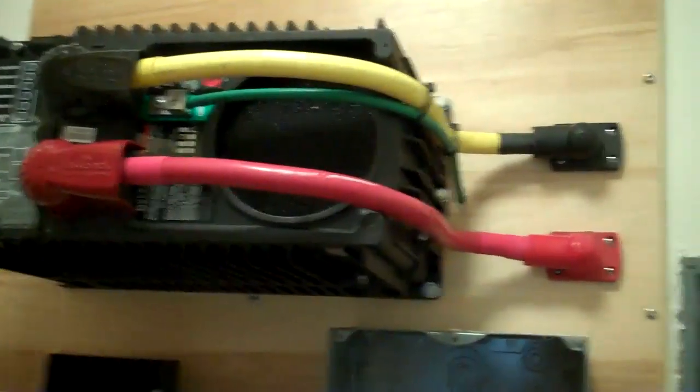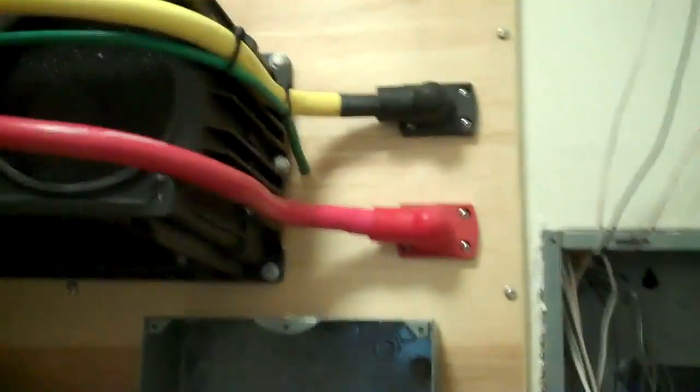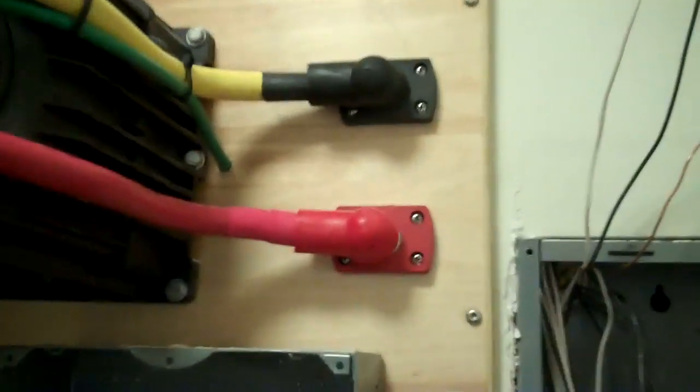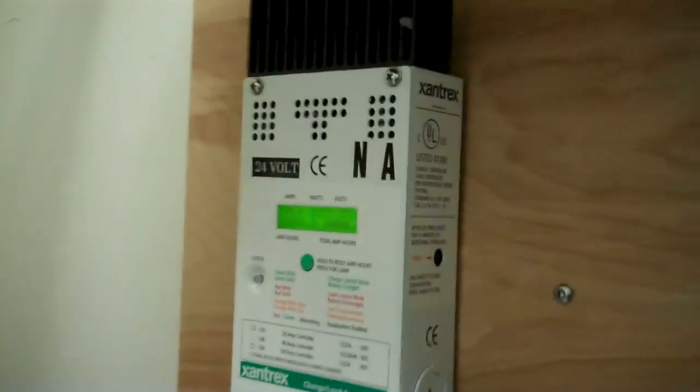We're done with the DC side of the inverter, it's hooked to those pass-throughs, it comes down, this is all in 4-Aught cable. Those two yellow are actually negative and positive, but we didn't have any red 4-Aught, but we wanted to keep running 4-Aught. Got the charger back up and running, hooks to the batteries over here with 4-Aught. But I'm going to overview some of that, I'll probably do a video after this one that'll just overview everything. But we've got a lot of work to do, it's Christmas Eve and they need to have lights and all tonight.